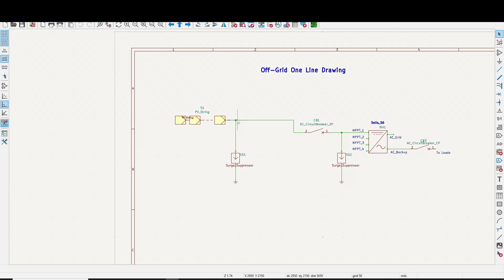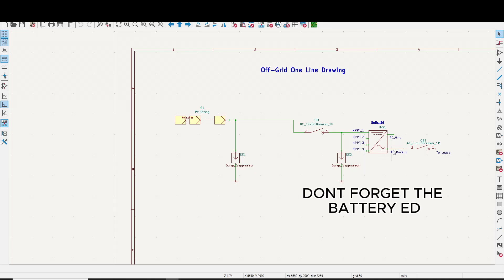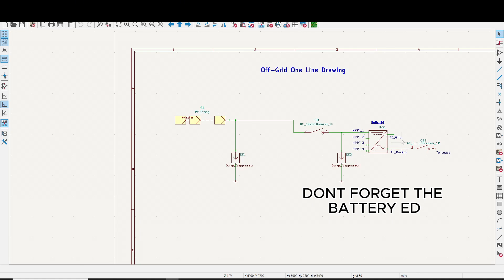After the solar panels, we like to put a surge suppressor in. And then we've got a DC circuit breaker before you go into the inverter. And another surge suppressor right before the MPPT input to the inverter. Here you've got the inverter. That's the symbol for an inverter. You've got the DC over here. So these are all DC inputs. And you've got the AC over here.